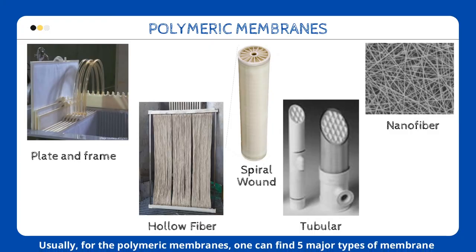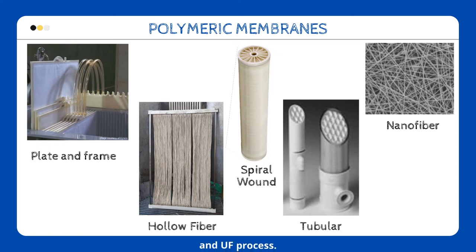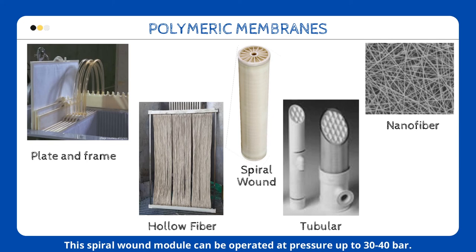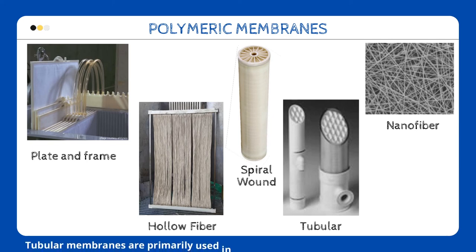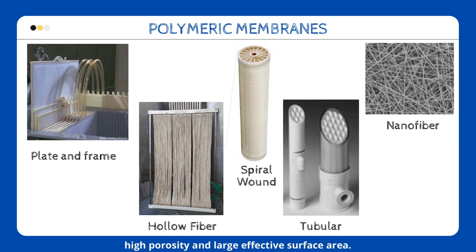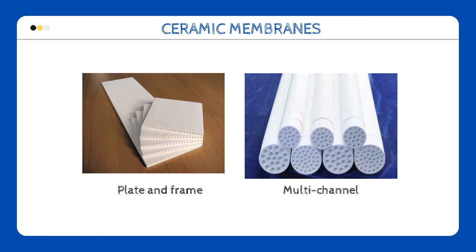There are quite a number of membrane configurations. For polymeric membranes, one can find five major types in the market. Plate and frame, as well as hollow fiber membranes, are typical configurations for microfiltration and ultrafiltration processes. Spiral wound membrane modules are used in nanofiltration and reverse osmosis processes, and can be operated at pressures up to 30 and 40 bar. Tubular membranes are primarily used in filtration processes due to their ability to handle process streams with high concentrations of solids. In recent years, nanofibre membranes are receiving great attention owing to their extremely high porosity and large effective surface area. For ceramic membranes, the two main configurations are plate and frame, and multi-channel ceramic.